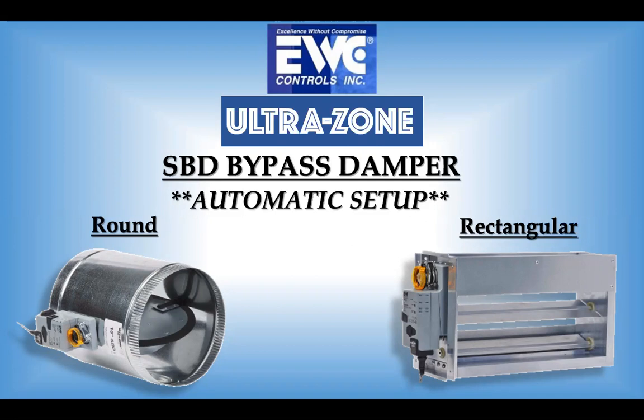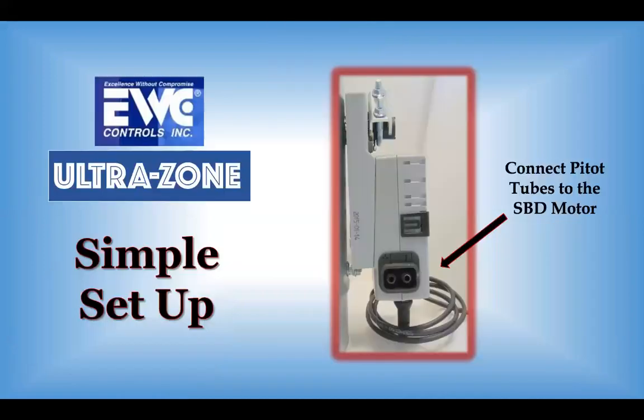It's a combination Belimo motor and built-in manometer pressure regulator, which you can see is located at the bottom of the Belimo motor. This will monitor and maintain the design static of any system in all modes. Now it comes with the pitot fittings and the tubing, and simply requires that you do a normal installation of a bypass damper, install those pitot tubes and pitot fittings, and wire it to a transformer.